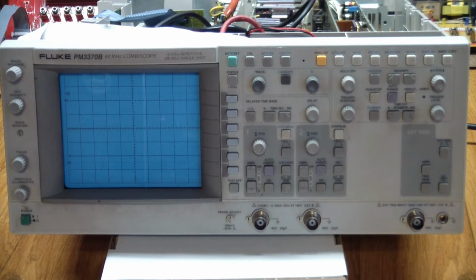So what I did, even though this may not have been the wisest thing to do, but I didn't know what else to check, I rechecked the components that I had replaced, and they were all still good. So I turned on the unit again, and approximately 30 seconds after it was on, I heard the loud crack again. This time, the instrument didn't turn off, but the screen disappeared. So what that tells me is we have to go on a corona hunt.